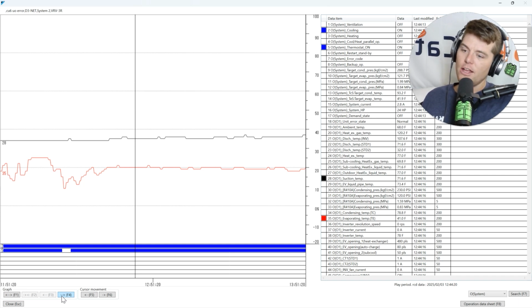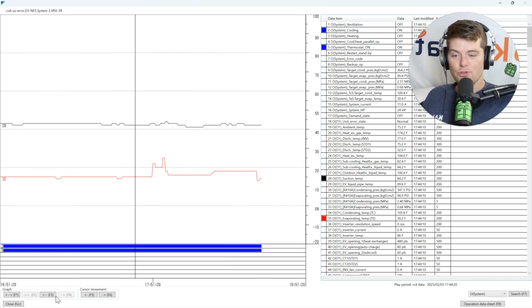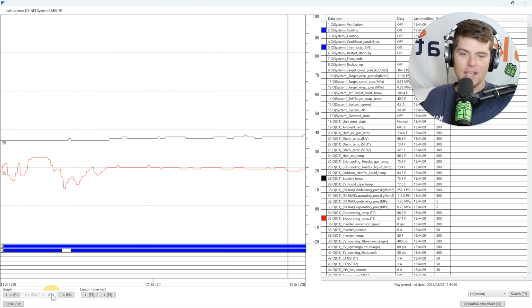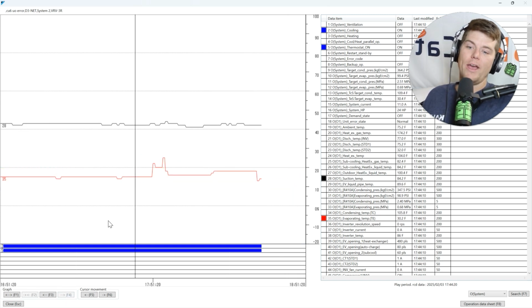into the system. And so don't be fooled that the charge looks okay in low demand, because again, it has enough refrigerant for that low demand. But what happens over time? Well, over time, when it goes to pull the liquid back out of that receiver, if there is any, the suction superheat drifts, and it drifts so much that at the beginning here, we go from a 30 to 28 degree suction superheat all the way up to a huge 56 degree split of suction superheat.